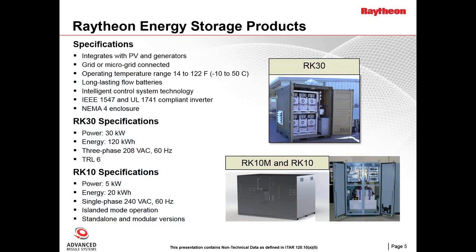General specifications for both the RK10 and RK30: they easily integrate with various power sources including PV, wind, generators, and the grid, and can support numerous applications. They can be connected to the grid or in a microgrid configuration, with a temperature range of minus 10 to 50 degrees C. The flow batteries have a long life — currently over 1,200 cycles. The control systems monitor temperatures, voltages, currents, and battery cycling. The inverters are grid-capable with IEEE 1547 and UL 1741 compliance. All enclosures are NEMA 4 rated. The RK30, housed in a Tricon, supplies 30 kilowatts with 120 kilowatt-hour capacity at 208 volts three-phase 60 Hz, and has met TRL 6 specs.